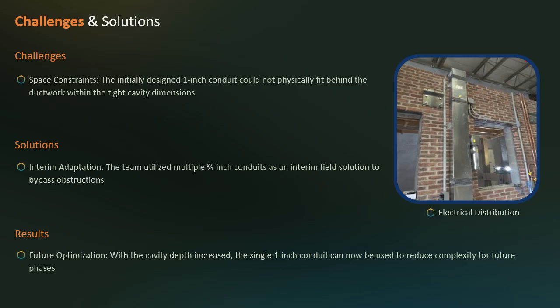Another issue with that 5.5-inch cavity was the conduits not fitting. There's low voltage power running to serve these facade-integrated terminal units, and the 1-inch conduit is technically more than 1 inch after the outside diameter is added, so it would just not fit. We had to run multiple 3/4-inch conduits instead, which made everything more complex - more coordination, more upgraded shop drawings, and more material wastage. Now that we have the 6-inch cavity, running the 1-inch conduit is much more straightforward.